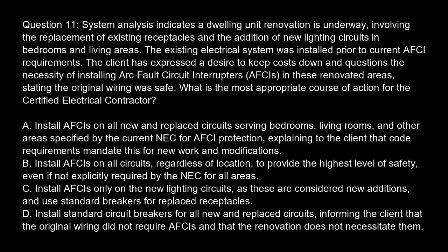Option C. Install AFCI only on the new lighting circuits, as these are considered new additions, and use standard breakers for replaced receptacles. Option D. Install standard circuit breakers for all new and replaced circuits, informing the client that the original wiring did not require AFCI and that the renovation does not necessitate them.